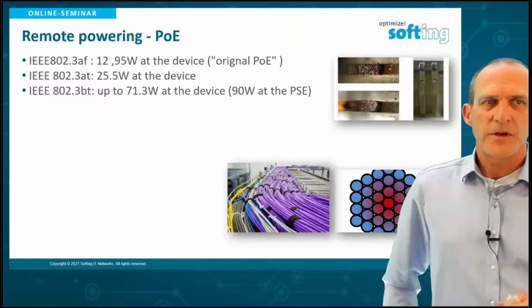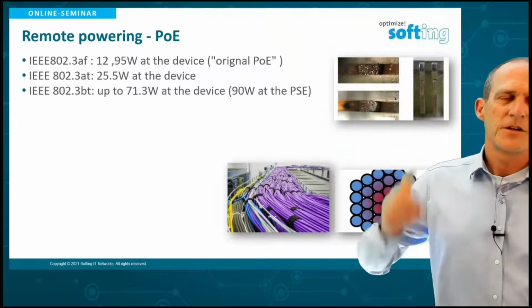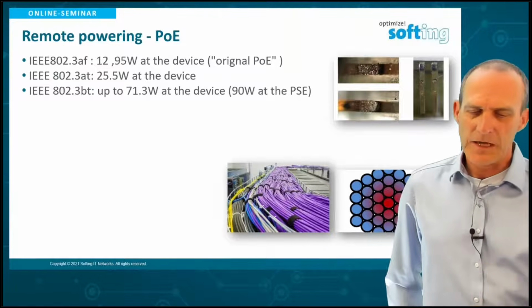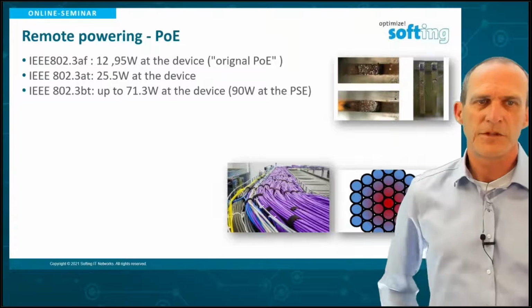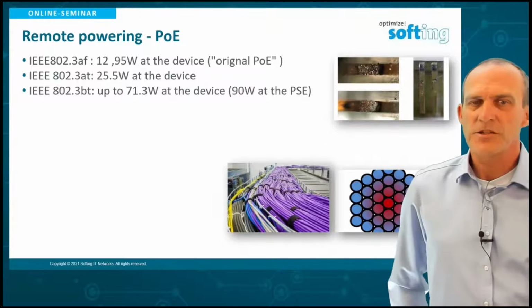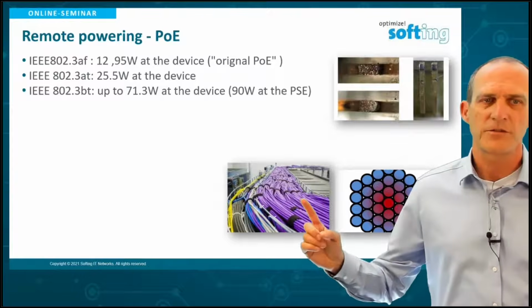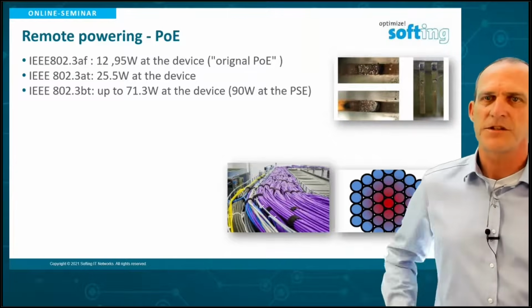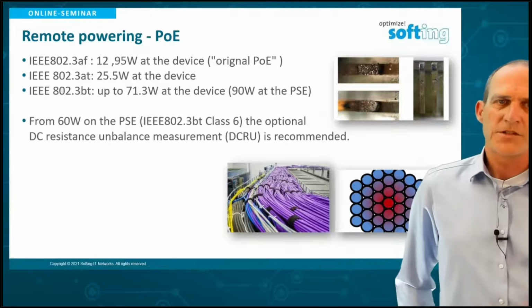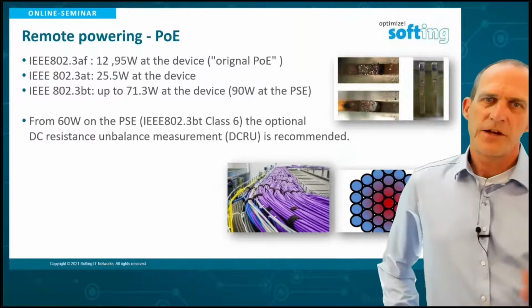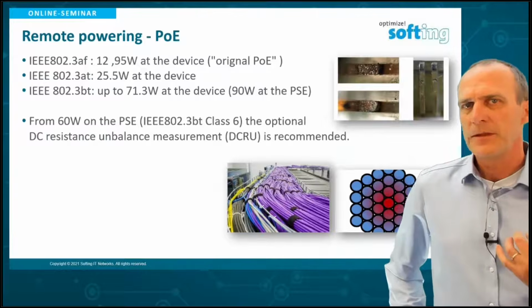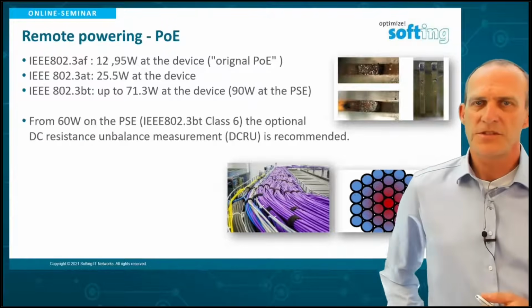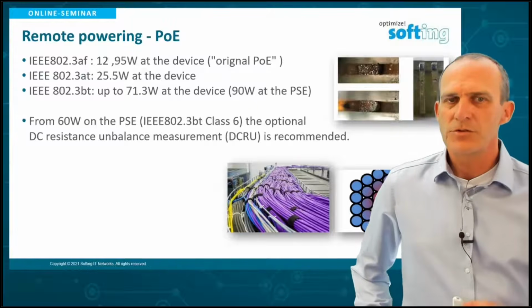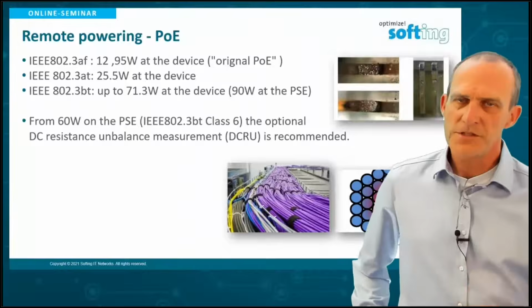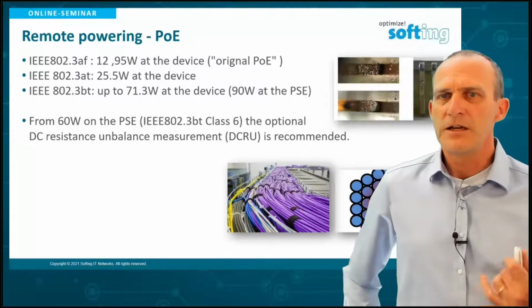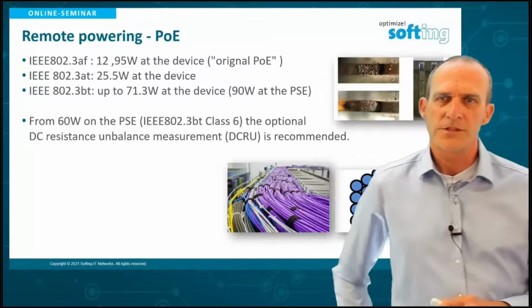You can see what happens on the right side here at the connectors. When you pull 90 watts of power under load, you get quite a bit of spark erosion. The other thing that happens is what you can see down here. If you have large bundles of cables like here, you get heating of the cables. So from 60 watts to 90 watts onwards, we recommend using DC resistance unbalance measurement to ascertain that the resistance of the individual wires of the cable is good or within tolerances.